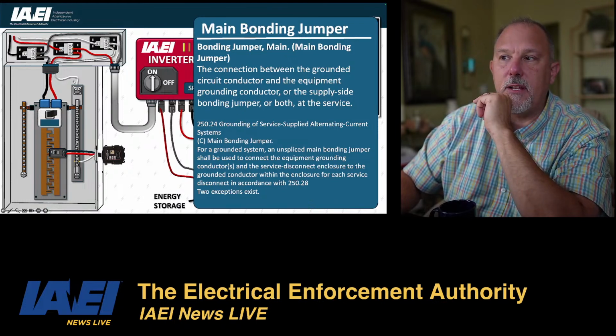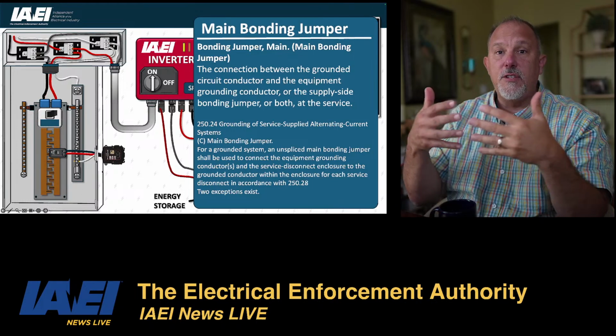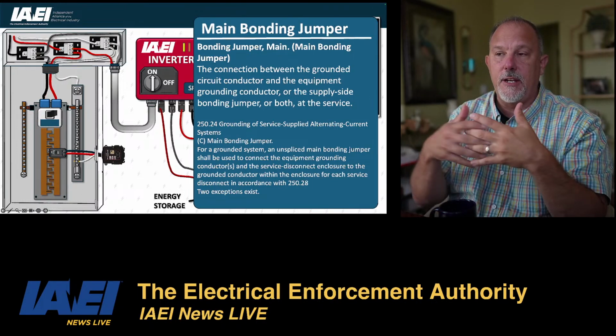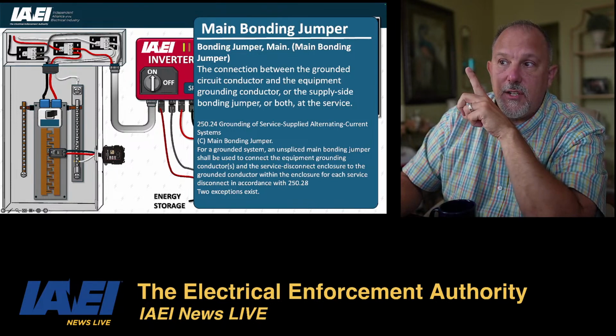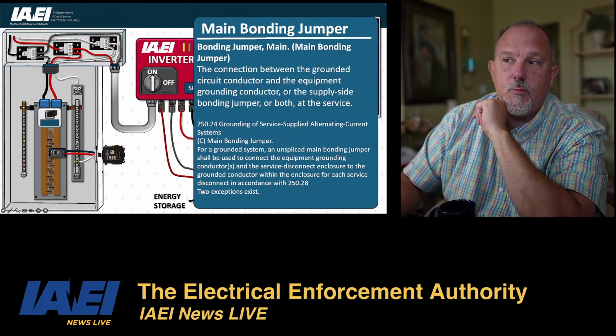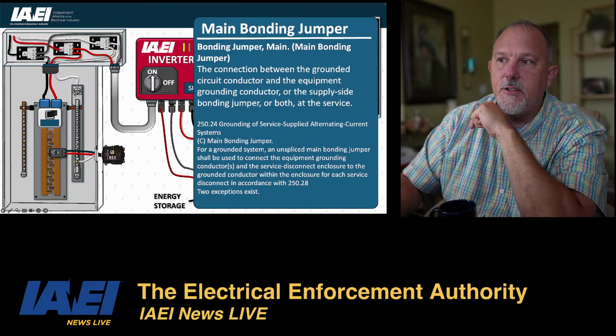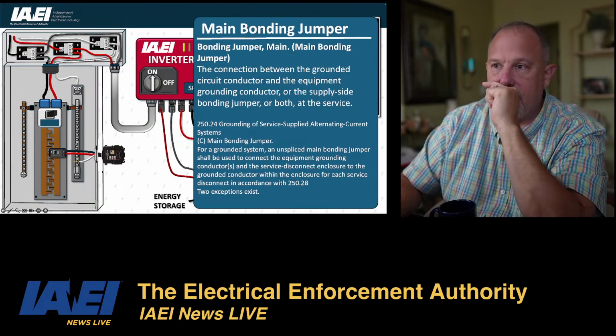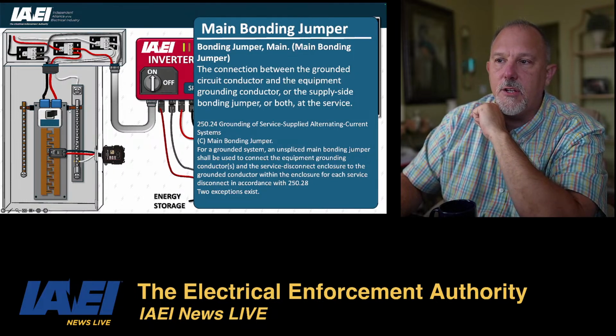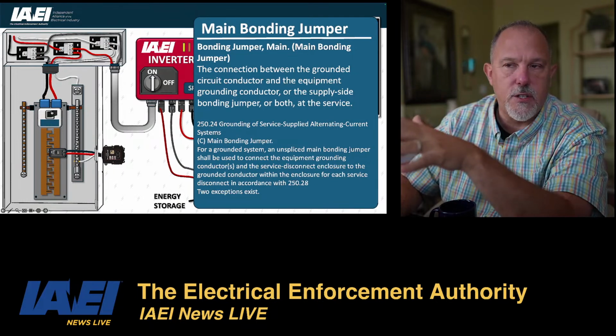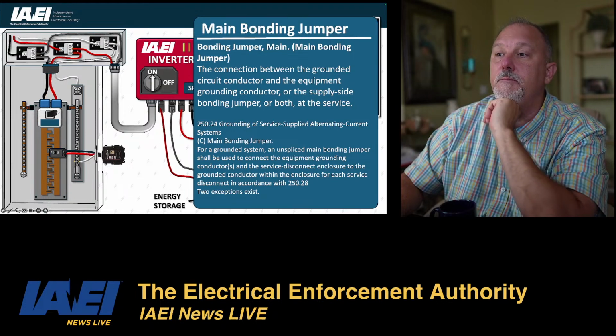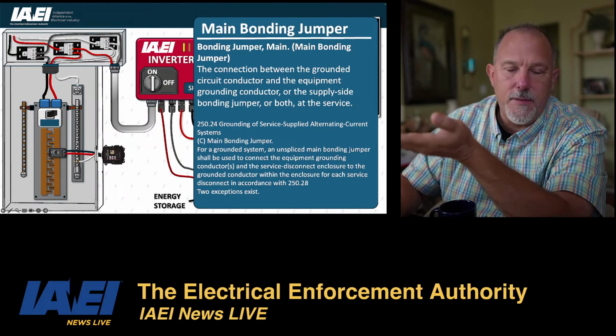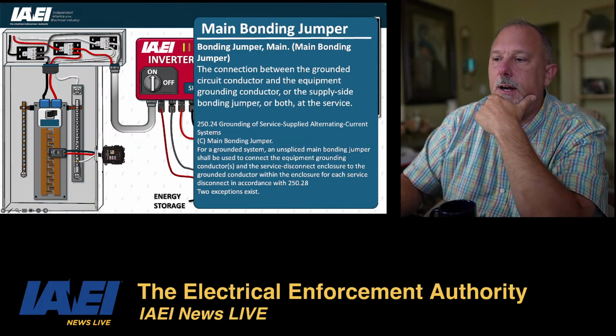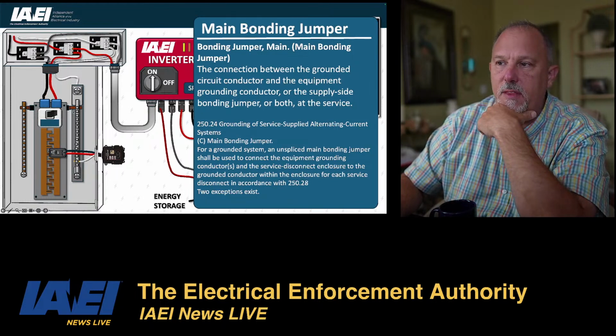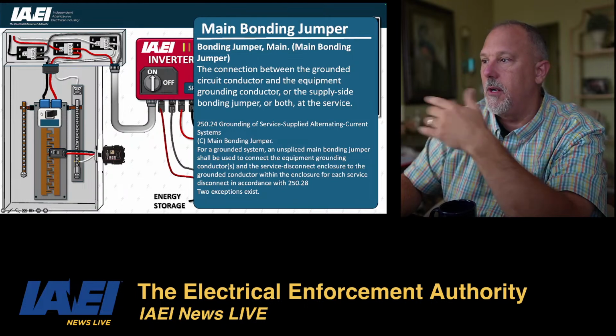Now we will typically, if that bonding strap is not there, because I can't use the back pan as my connection, I could elect, if that bonding strap is there, then I could land this grounded conductor either on that neutral or on the equipment grounding bar, either one, as long as there's a main bonding jumper in, that's a physical bonding jumper, and I'm not using the back pan. But we always land it on this neutral bar, this grounded bar, which is insulated from the panel, but then bonded through the main bonding jumper.